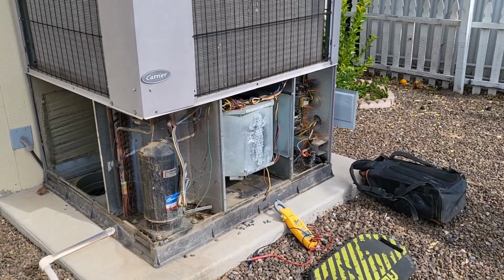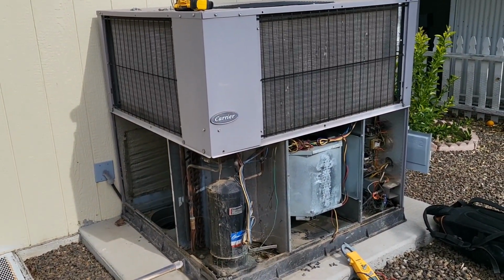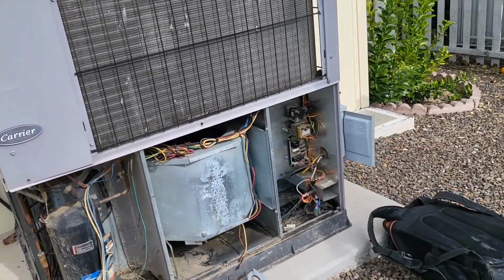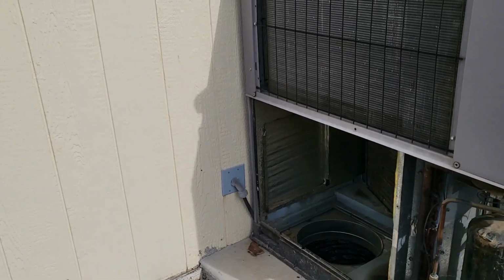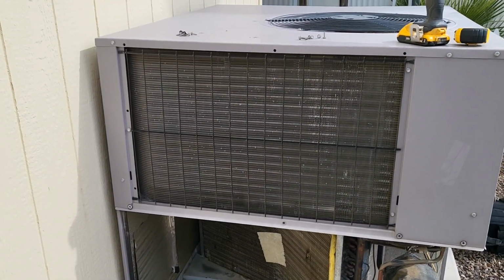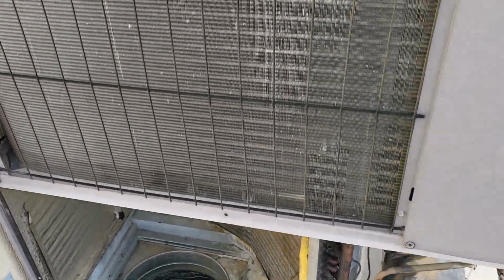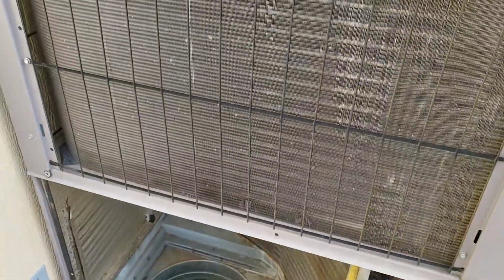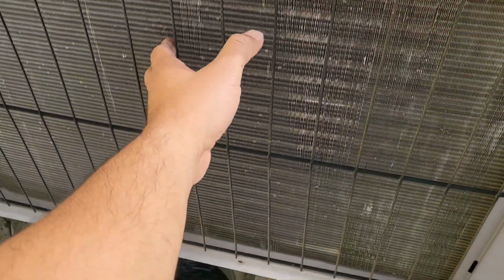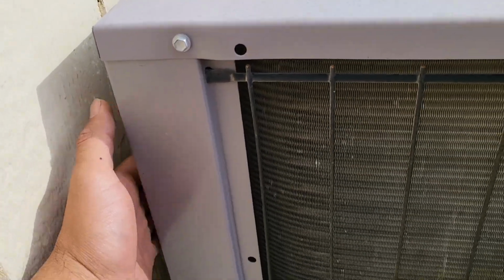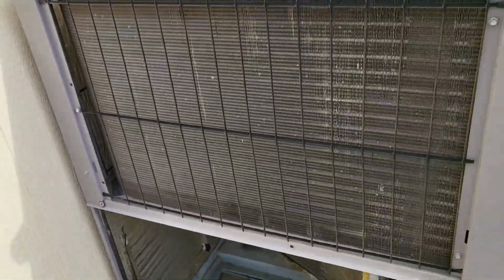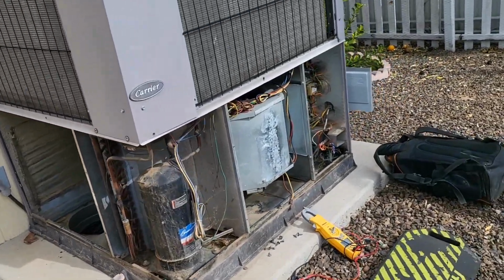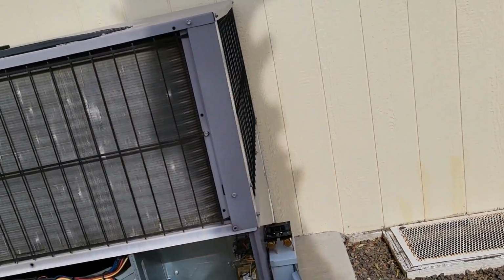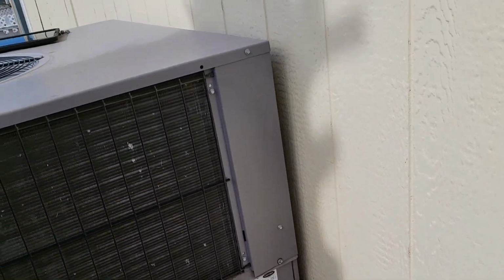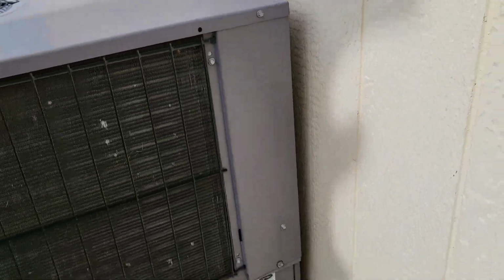We got another one of the calls that turns out to be a hack job that did the work. If you notice right here, right off the bat, if you know anything about these heating and cooling systems, you know that these coils have to be kept cool and have to have some clearance to breathe, right here. Well, you obviously don't have that in this application. See, only 3 sides are getting airflow and the 4th side is not getting very much.